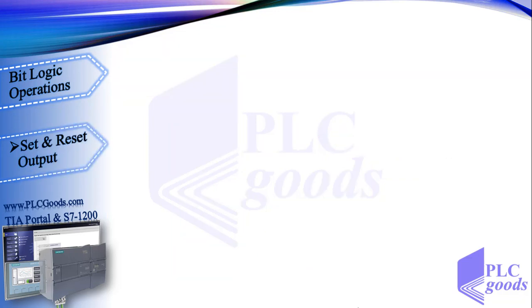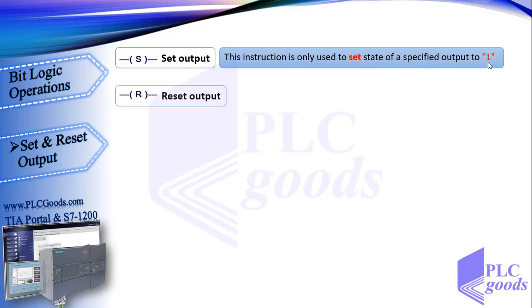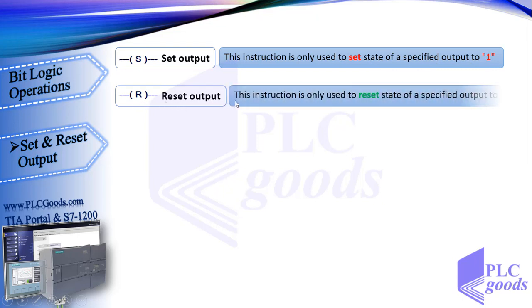Now let's see set and reset instructions. Their meanings are related to latching and unlatching. This is the set instruction symbol. Its difference with assignment symbol is the S letter. This instruction is only used to set the state of a specified output to 1. Reset instruction with this symbol is only used to reset the state of a specified output to 0.